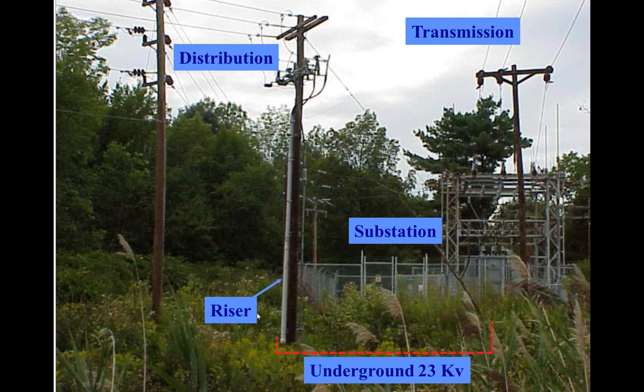Now, this thing on the side here, this riser, very, very important. All of you start looking for these. If you see a plastic PVC pipe or a pipe on the side of that pole, that is typically how the utilities get primary voltage conductors from the top of the pole to the bottom of the pole. So if you're ever weed whacking or backing into something, you've got a snow plow, and you damage one of these things, or if you've got a vehicle that's hit one of these things, you have got an electrical event, and you've got to take the right actions. We're going to talk about those actions in a few minutes. But look for those things. They're everywhere. And that's how we get primary voltage conductors up and down the poles in those PVC pipes.